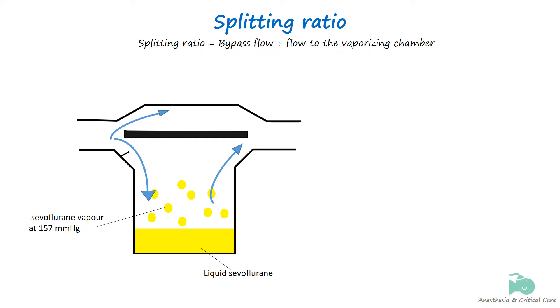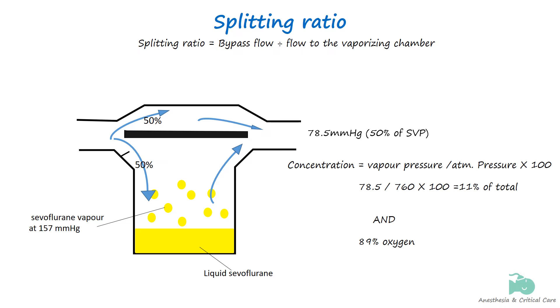For instance, if we send 50 percent into the vaporizing chamber and 50 percent through the bypass channel, we can halve the resultant concentration of sevoflurane in the gas flow. This is because we only saturate half of the total gas with sevoflurane. Our resultant concentration is half the SVP, or 11 percent.